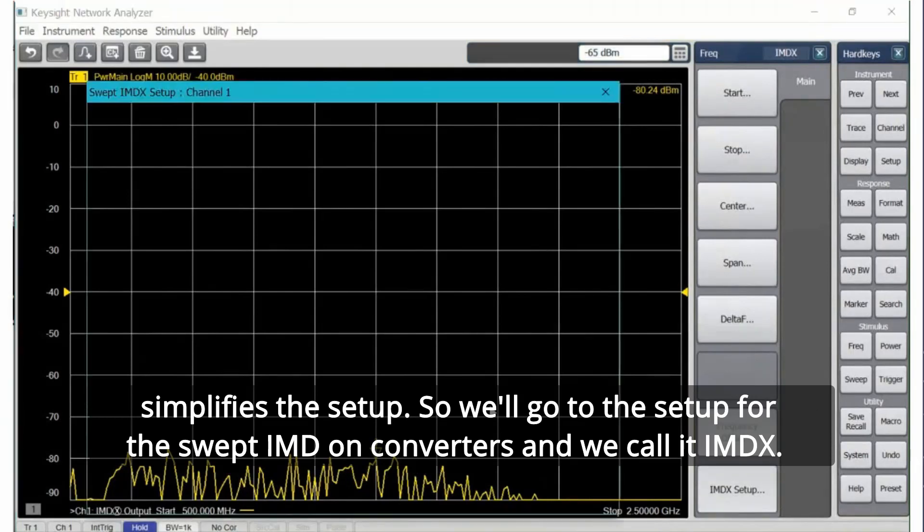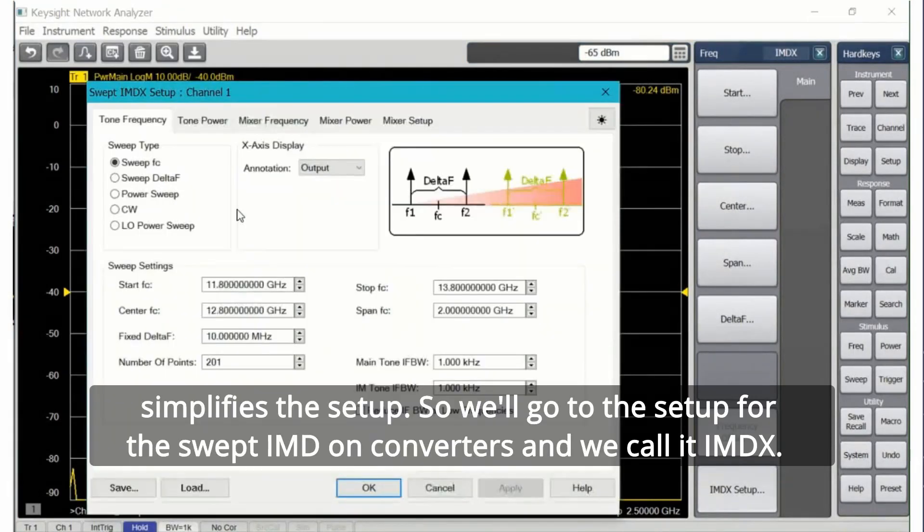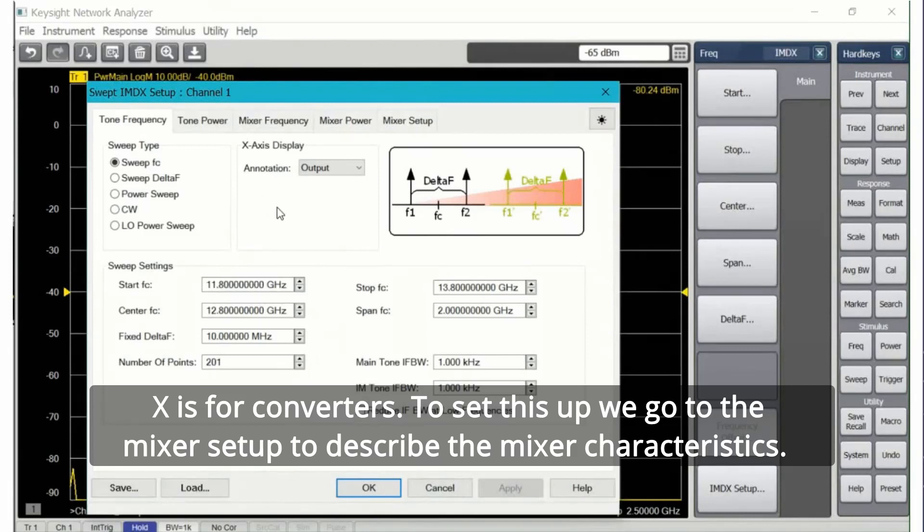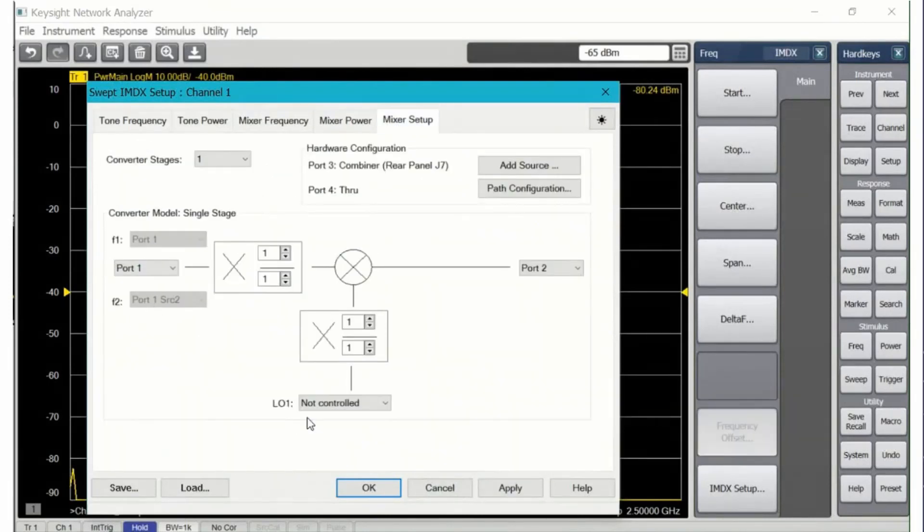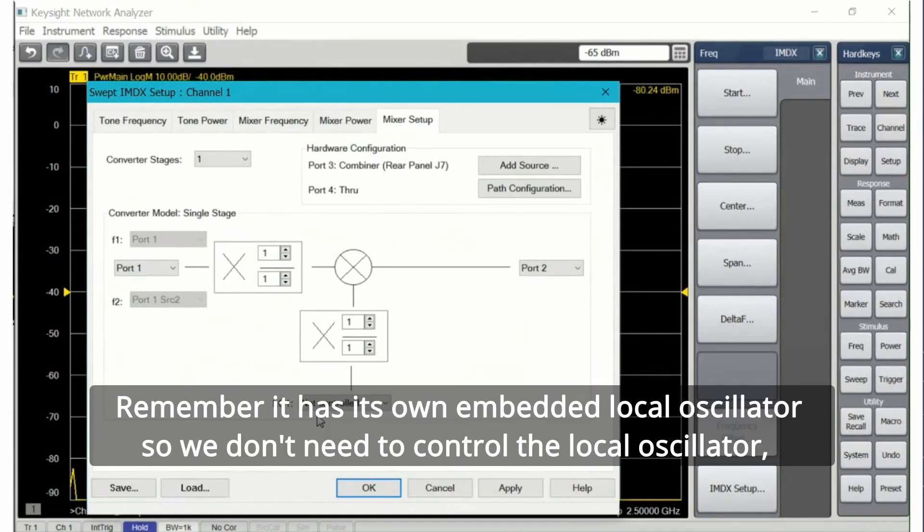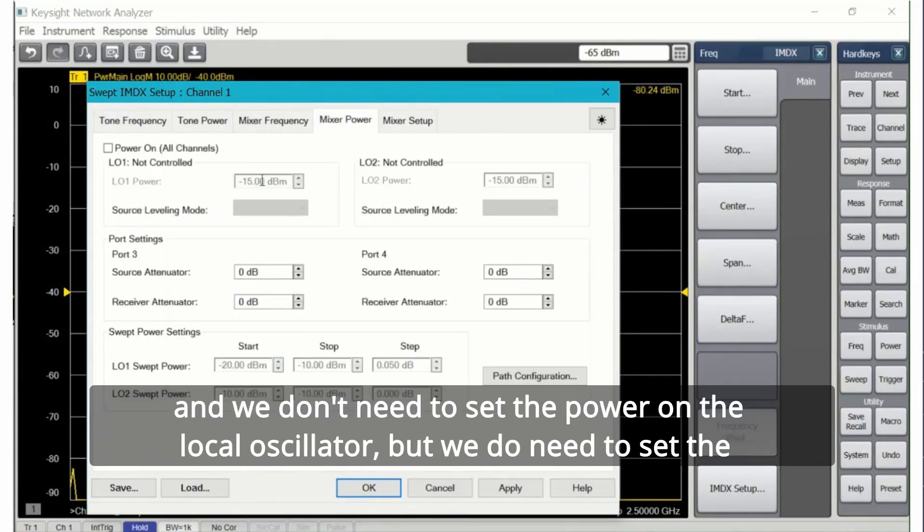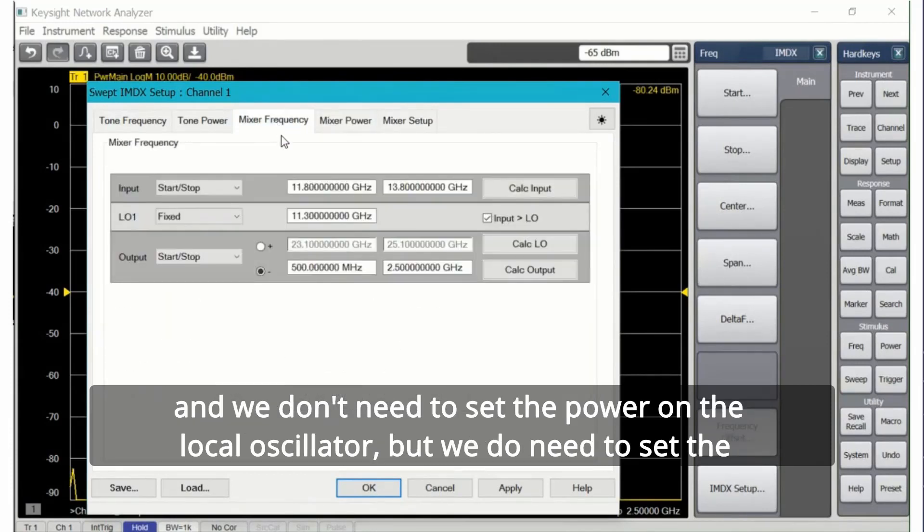This greatly simplifies the setup, so we'll go to the setup for the swept IMD on converters and we call it IMDX. X is for converters. To set this up we go to the mixer setup to describe the mixer characteristics. Remember it has its own embedded local oscillator.